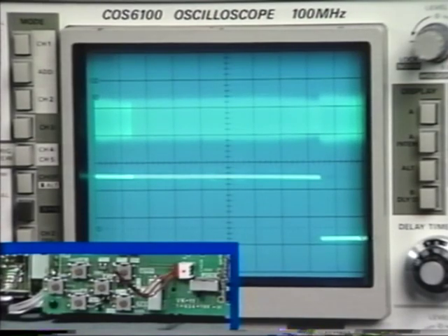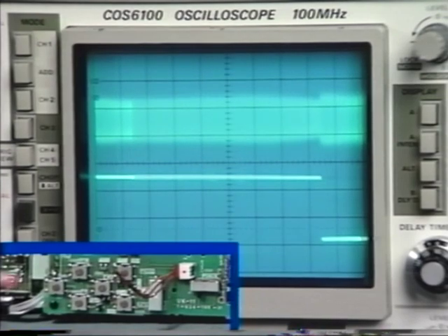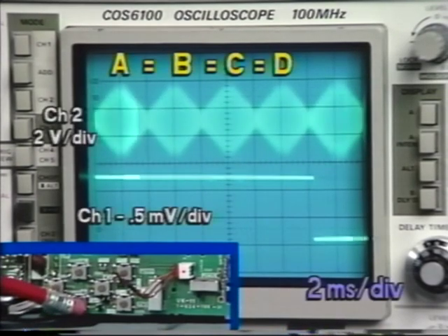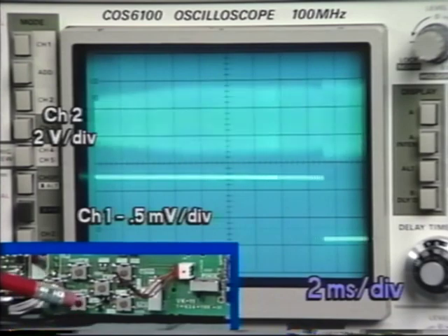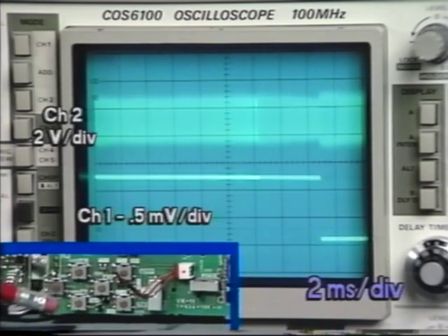Next, press fast forward while in play to execute the Q mode. Confirm that the RF envelope peaks still maintain a constant pitch for 5 seconds or more. The RF envelope should also return to a flat condition within 2 seconds of releasing fast forward.